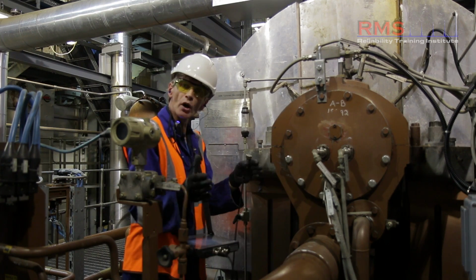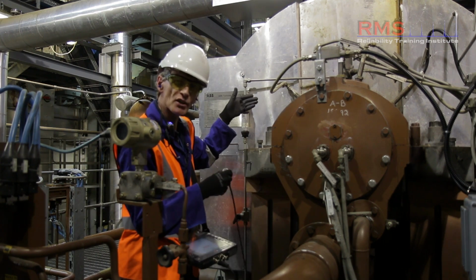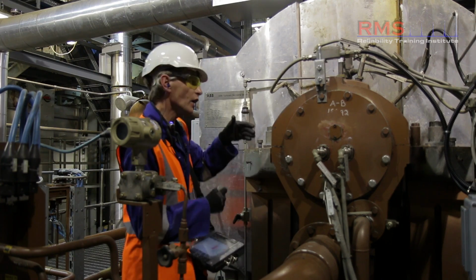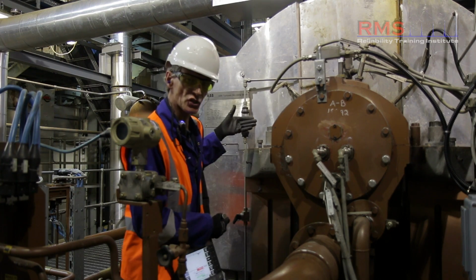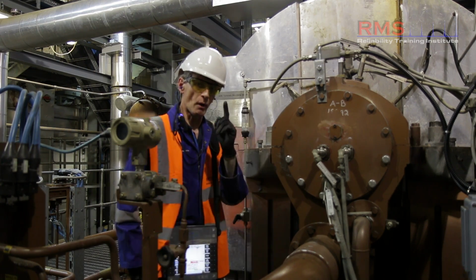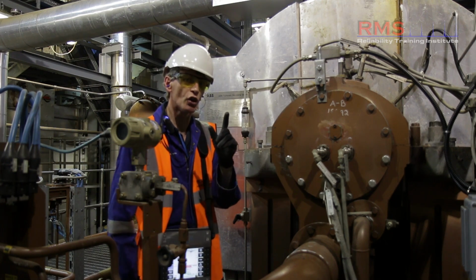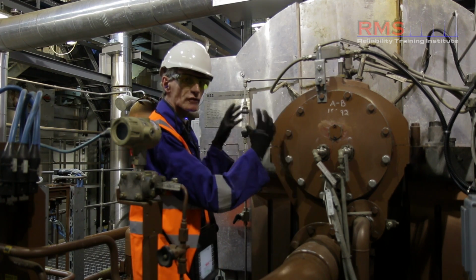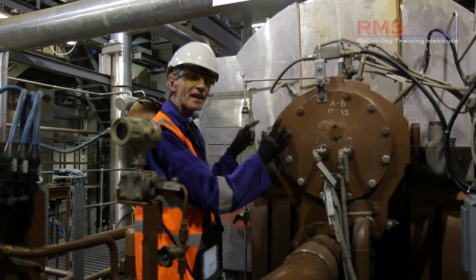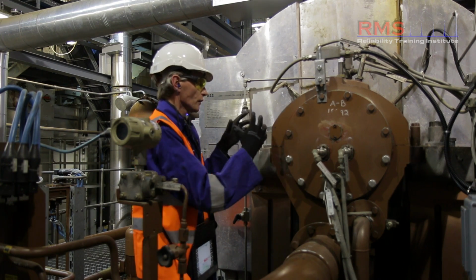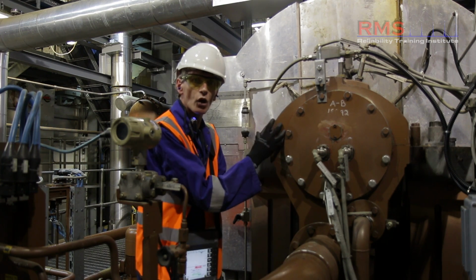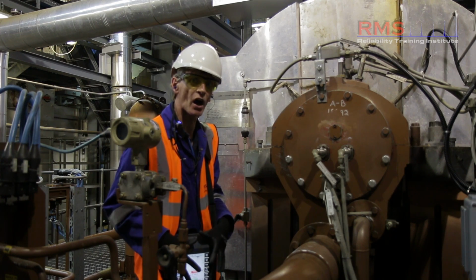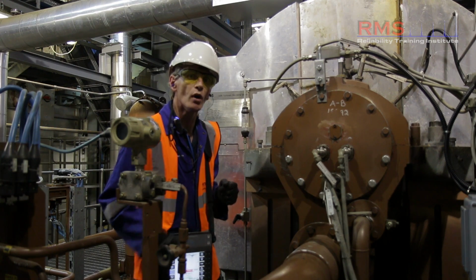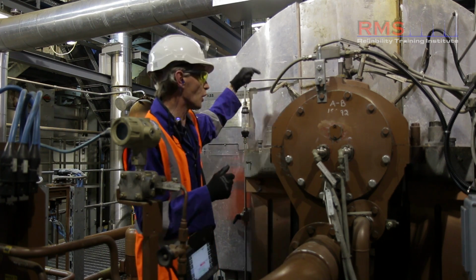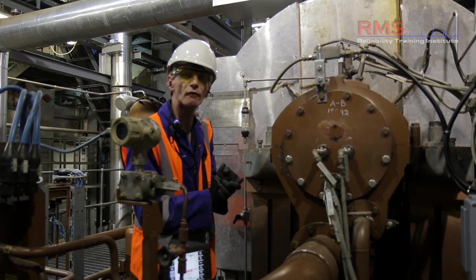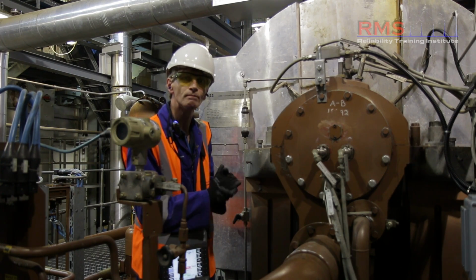Okay, I would then move on to measure the low pressure end of the turbine in the same way, the gearbox and indeed the generator. But as we said before, it's very important we also measure the dynamics of the shaft itself. So we now need to measure the dynamic movement of the shaft with our signal data acquisition device in the control room, where we can plug into remote probes that reflect the X and Y probes of this bearing pedestal.